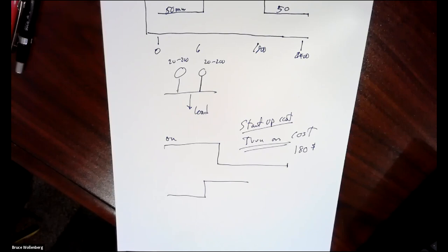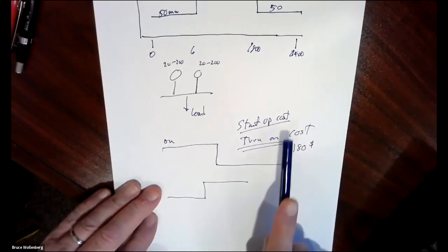You close the breaker and now you push more energy through the turbine and start to deliver power into the system. But that whole process from starting the boilers until synchronization has used a lot of energy. So that's the startup cost. It costs you something to get to that point, even though you haven't delivered any power into the system. Anyway, so this is the problem.